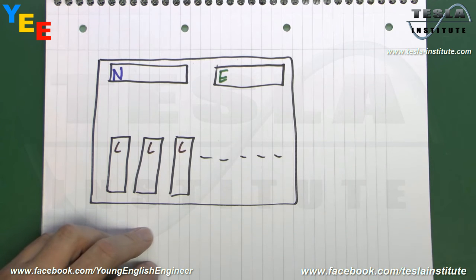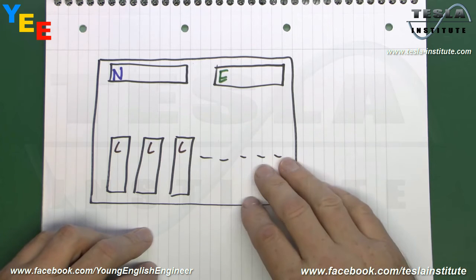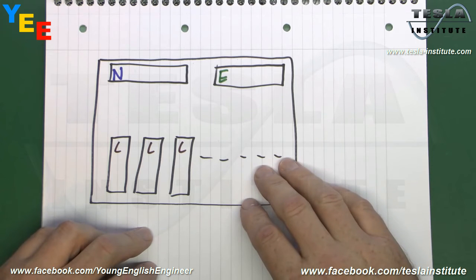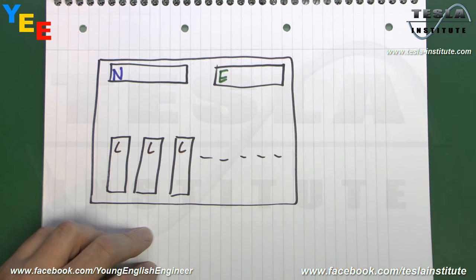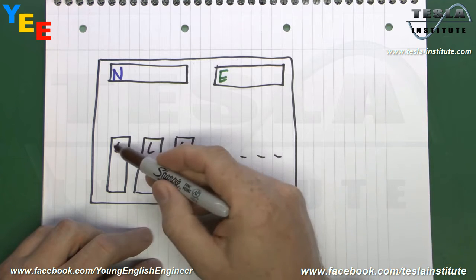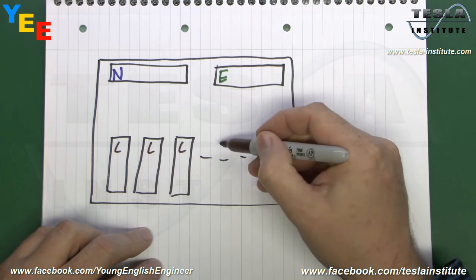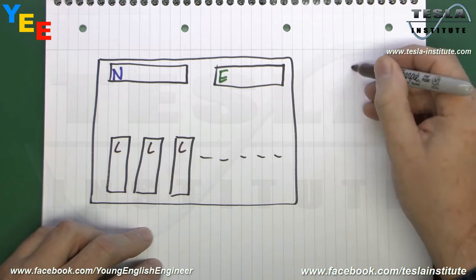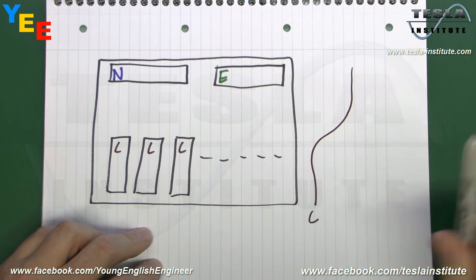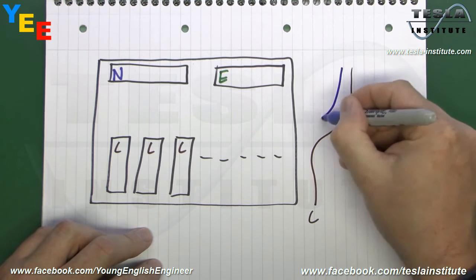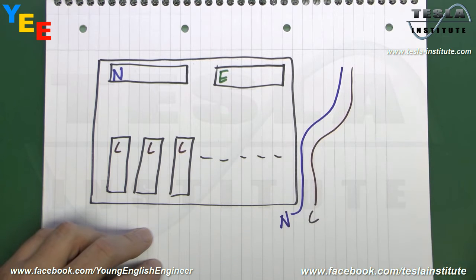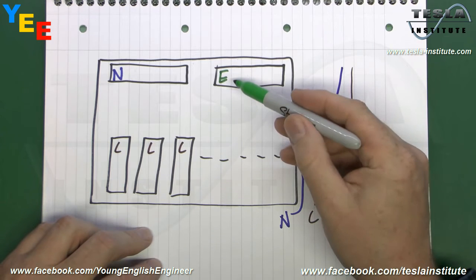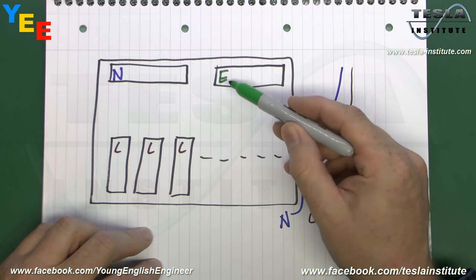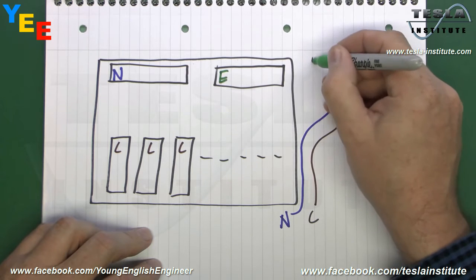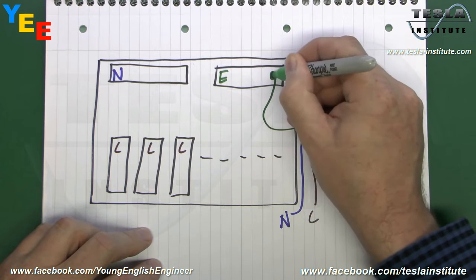And this test is done with the power disconnected, of course, and in the case of a new installation this test will be done before any power was even put anywhere near it. So no power is actually applied here. So if you've removed your wires from here, you'll basically have your wires coming out of there. So you have your line conductor here, the neutral there, and then the protective conductor or earth needs to be kept connected to the consumer unit. So in this case it would actually just be going into the consumer unit like this.